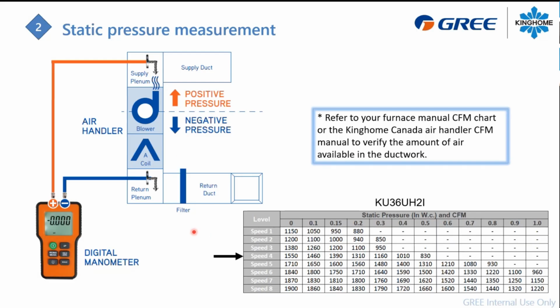When you have this number, you can always refer to your furnace manual, or instead, I put here an example of the electric heat air handler. So then you can always refer to this number right here. This is your static pressure. This system can be used from 0 to 1.0 static pressure. So anything between that, you need to match the proper speed to get the right amount of CFM through the coil. So just remember that for all kinds of installation, you need to have 325 CFM per ton as a minimum, and you can go higher than 400.